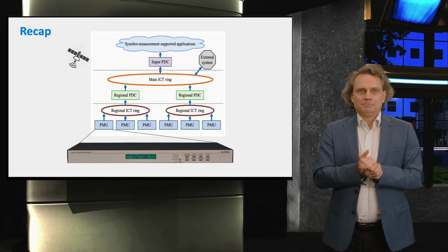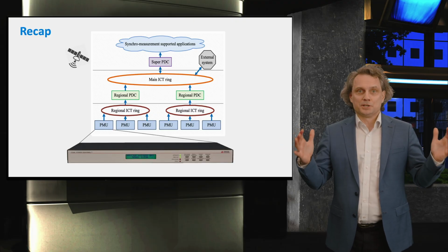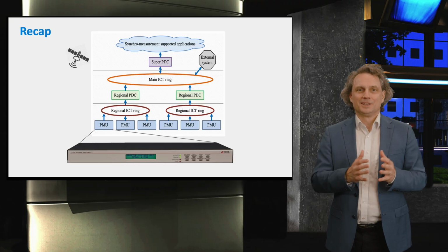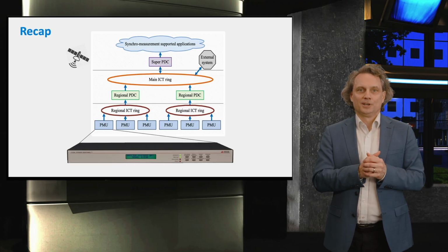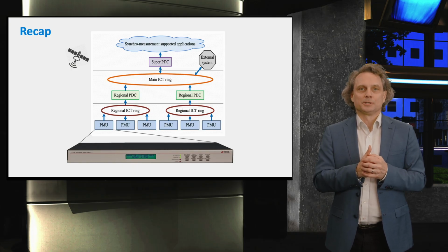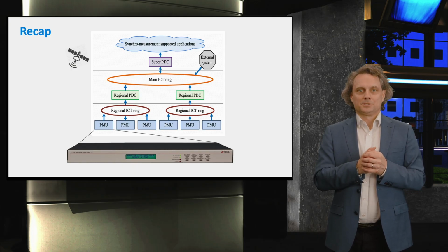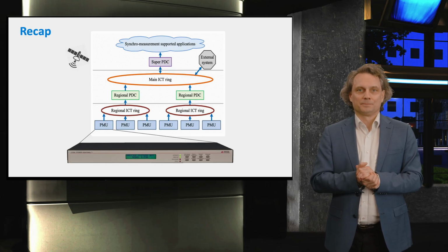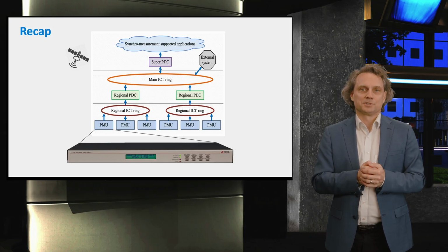So, you've seen the ecosystem of synchronized measurement technology. The central element here is the PMU, the phasor measurement unit, connected to communication infrastructure that transports the data. You can subscribe to a stream of data that contains estimated phasors of your sinusoidal measurement values in the substation. And they provide a high-resolution picture of the power system that you need for modern power system operations.